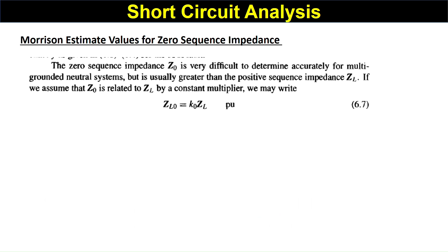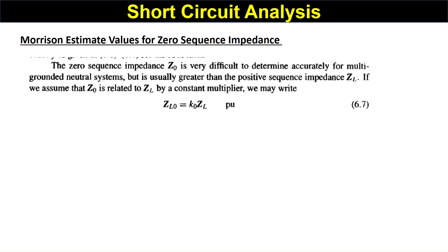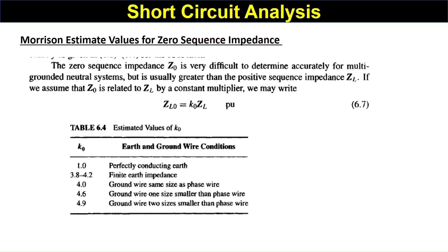For zero sequence impedance, according to the reference, Z0 is very difficult to determine accurately for multiple grounded neutral systems, but it is usually greater than the positive sequence impedance ZL. If we assume Z0 is related to ZL by a constant multiplier, we may write Z0 equals K0 times ZL. A table of estimated values of K0 is provided, and accordingly you calculate the zero sequence impedance.